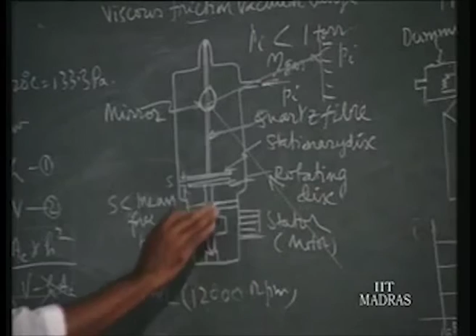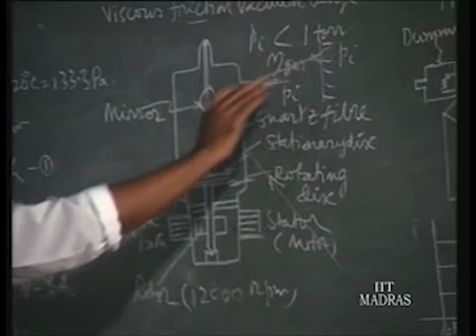So due to the torque, it will tend to twist. That is, we have got a quartz fiber with its elasticity, it will tend to twist. And you have a light ray from a source, and it will be reflected to an optical scale. So the optical scale is written in terms of vacuum pressure. So for different pressures we can get the reading, and for each gas we have to calibrate this instrument. After calibration we can use it.